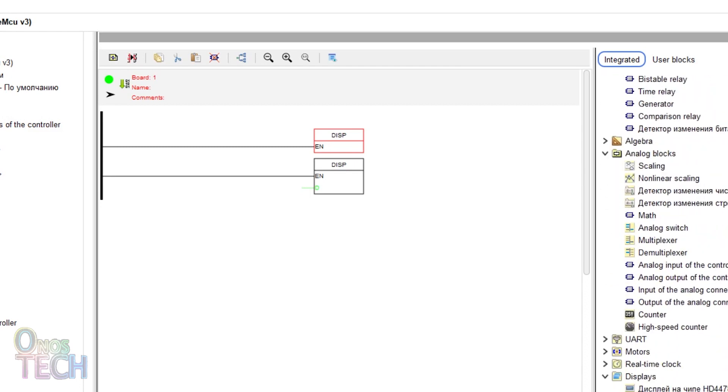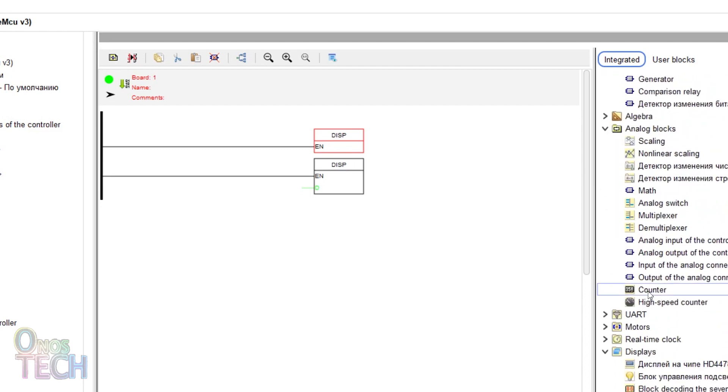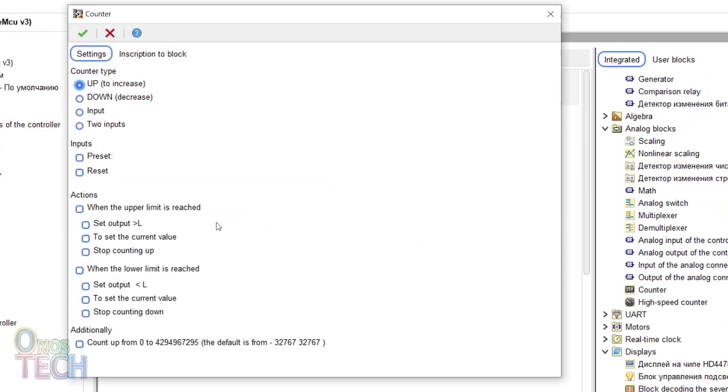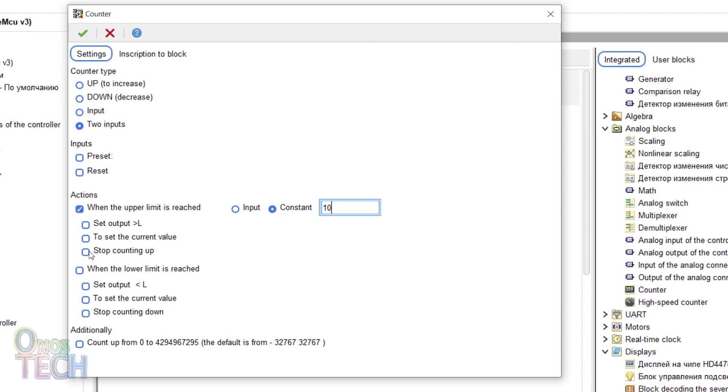Insert a counter into the program and set the counter type to the two input type. Enable the action when the upper limit is reached with a constant value of 10 and it should also stop counting up. Also enable the action when the lower limit is reached with a constant value of 0 which should also stop counting down.